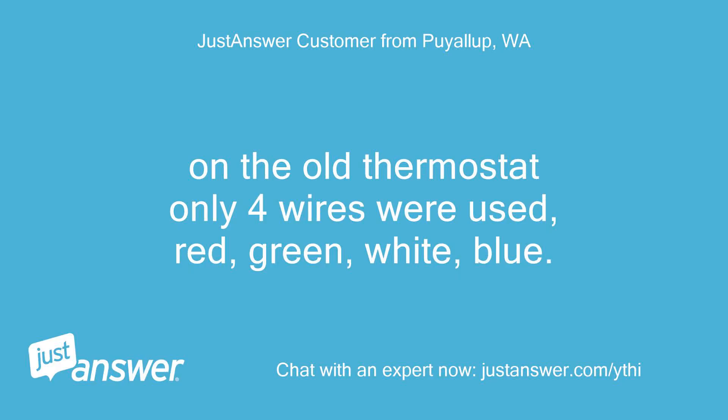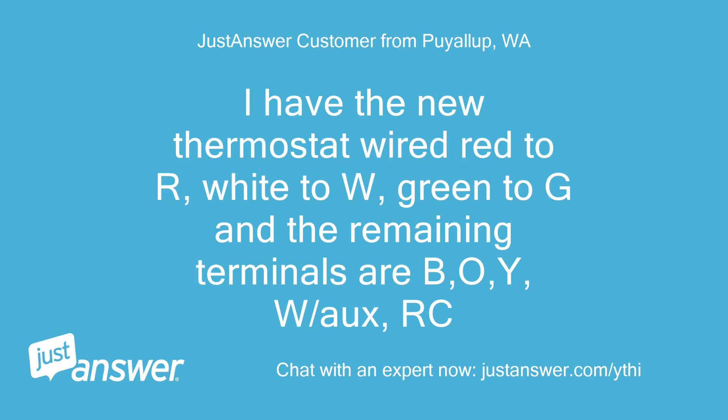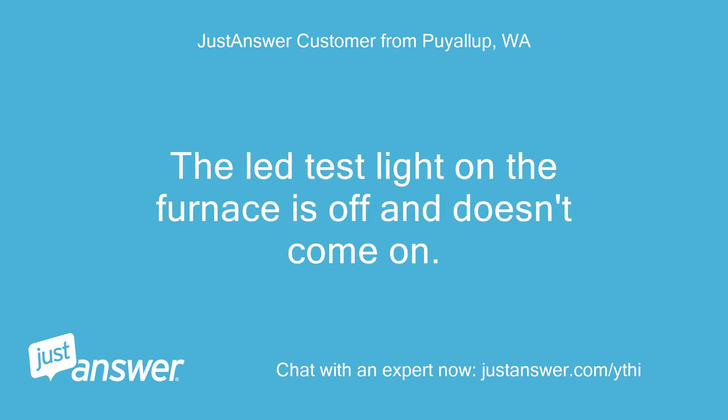On the old thermostat only four wires were used: red, green, white, blue. I have the new thermostat wired red to R, white to W, green to G, and the remaining terminals are B, O, Y, W/aux, and RC. The LED test light on the furnace is off and doesn't come on.